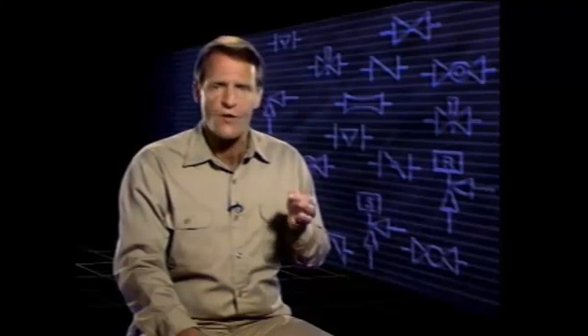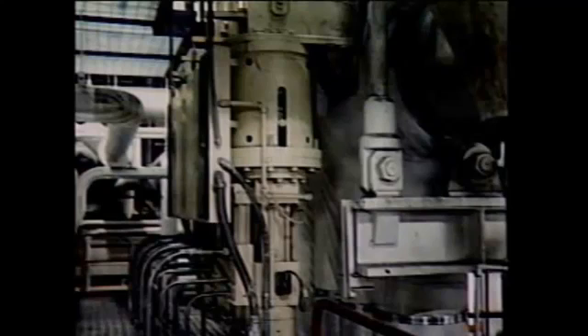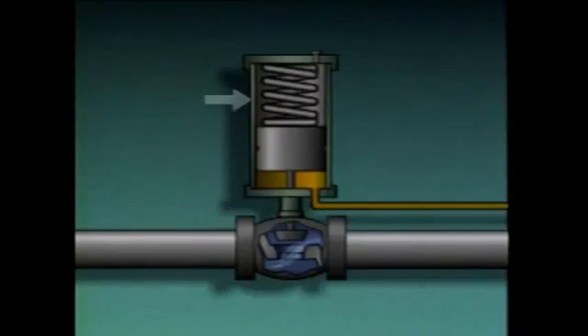Hydraulic actuators generally develop more force than similar-sized air-operated actuators. This is because some of the force exerted on an air-operated actuator is used up compressing the air, whereas liquids are not compressible. So more of the force goes directly toward positioning the valve. This power makes hydraulic actuators very suitable for operating large valves.